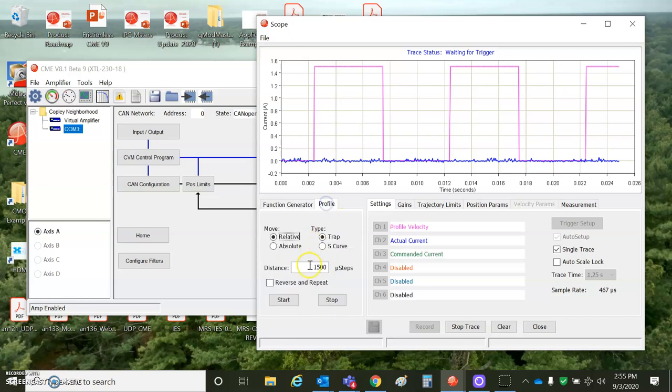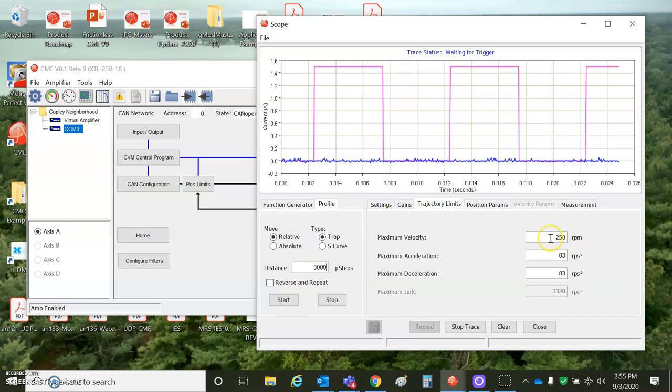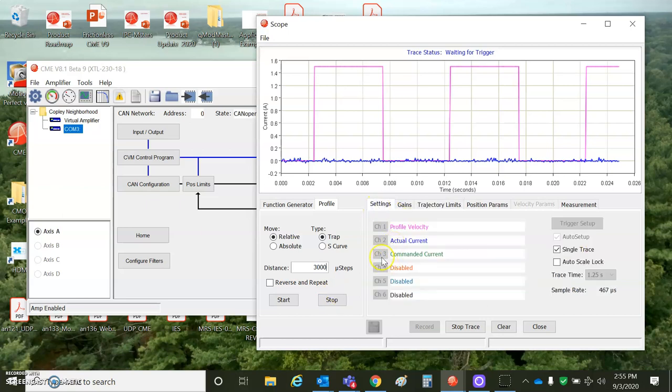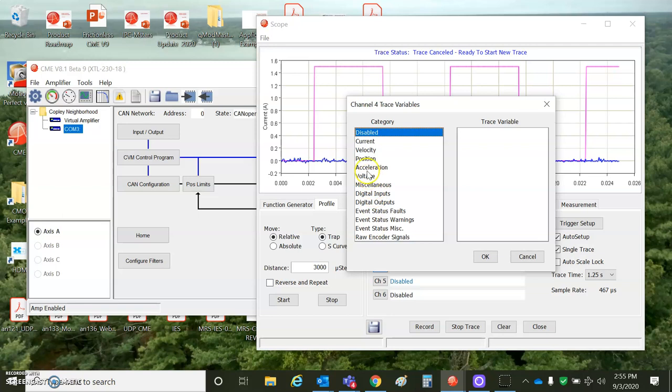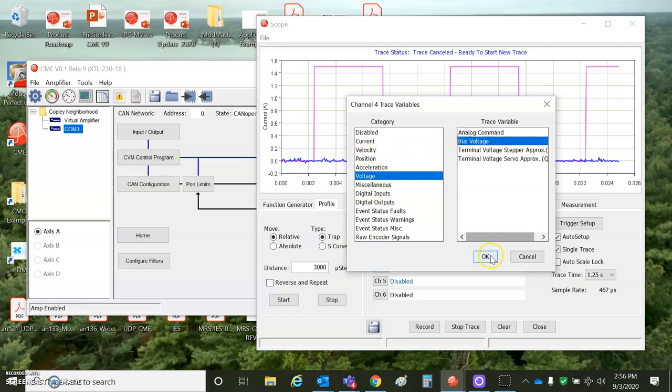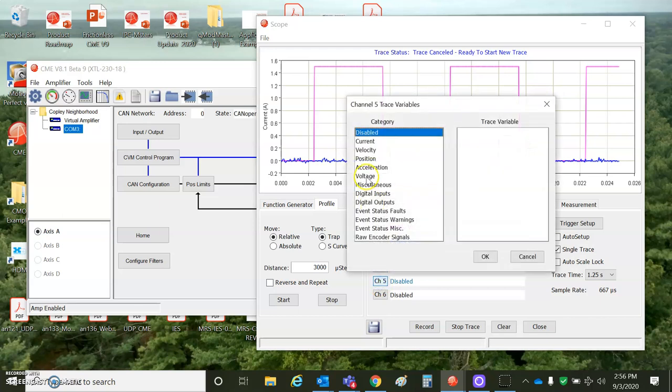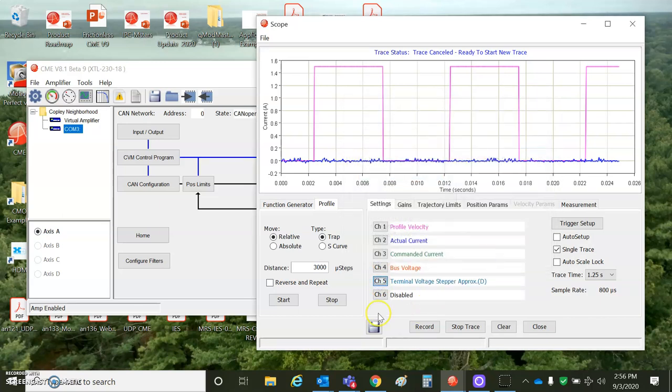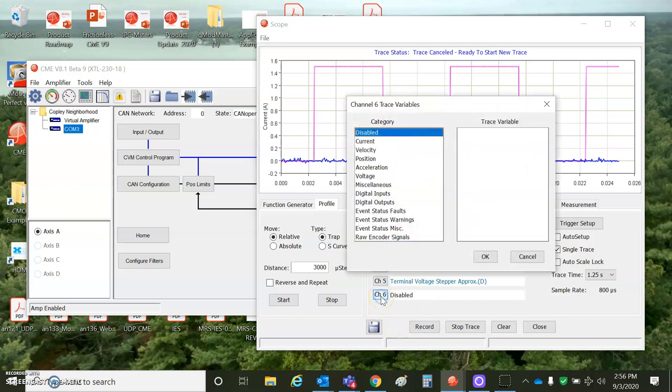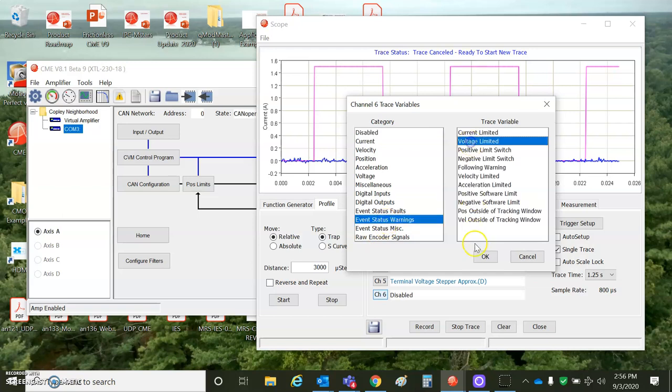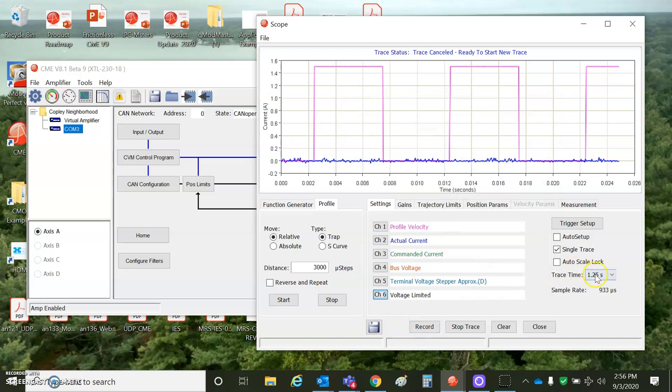What I'm trying to show you here is one rev is 3,000 microsteps, 250 RPM. That's the default calculated values. We're going to also take a look at voltage bus to see what our bus voltage is. We're going to look at voltage terminal stepper to see what the back EMF is plus the IR drop. It's a field-oriented control. So, this will be the imaginary part, which is predominant. There's still a real part, which the phase for a stepper is not 90 degrees, but in line with the flux field. So, there's a real component, too. But we'll look at the event status miscellaneous voltage limit warning, and we'll make the move.